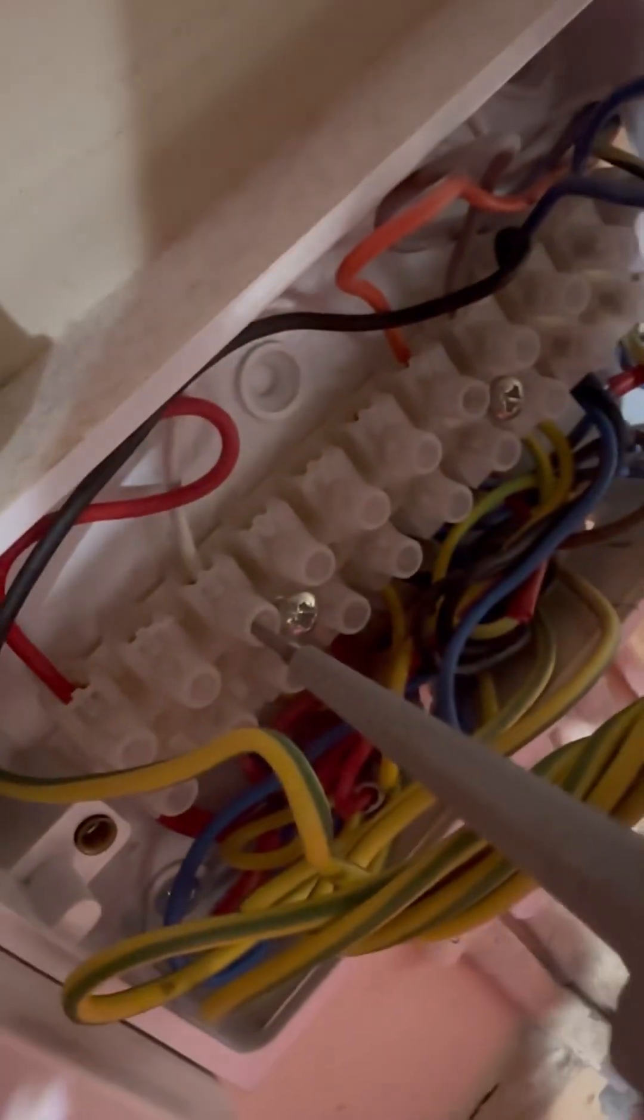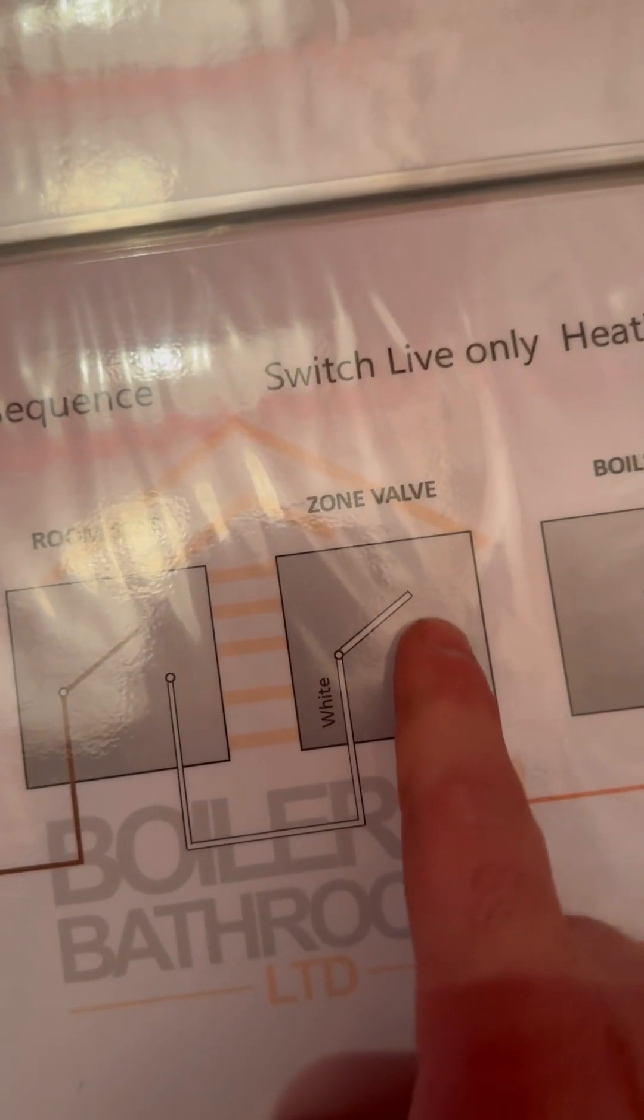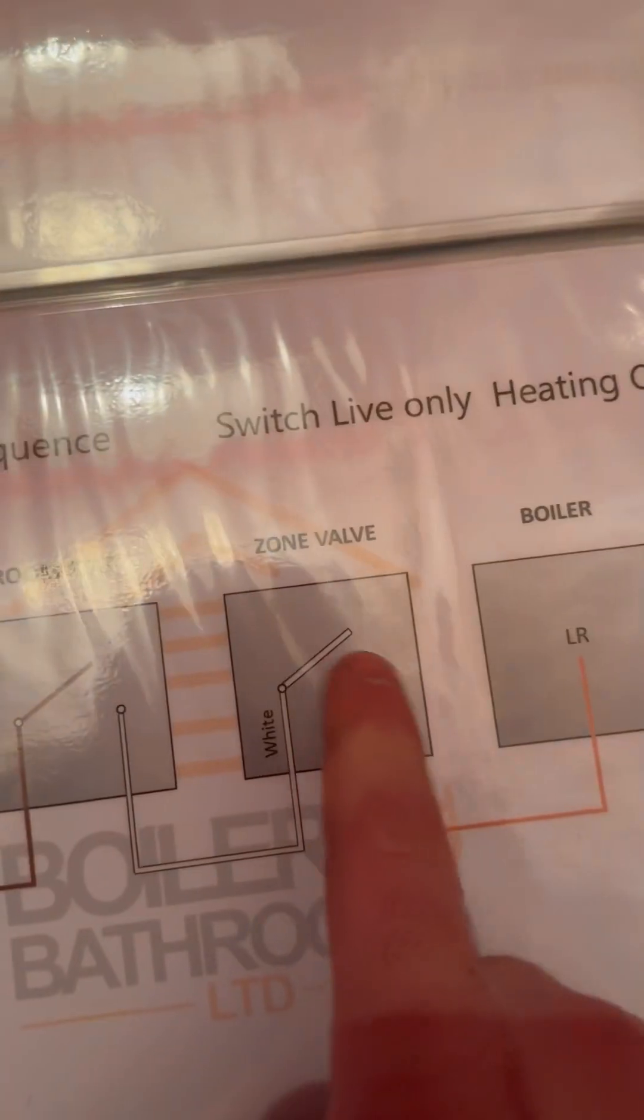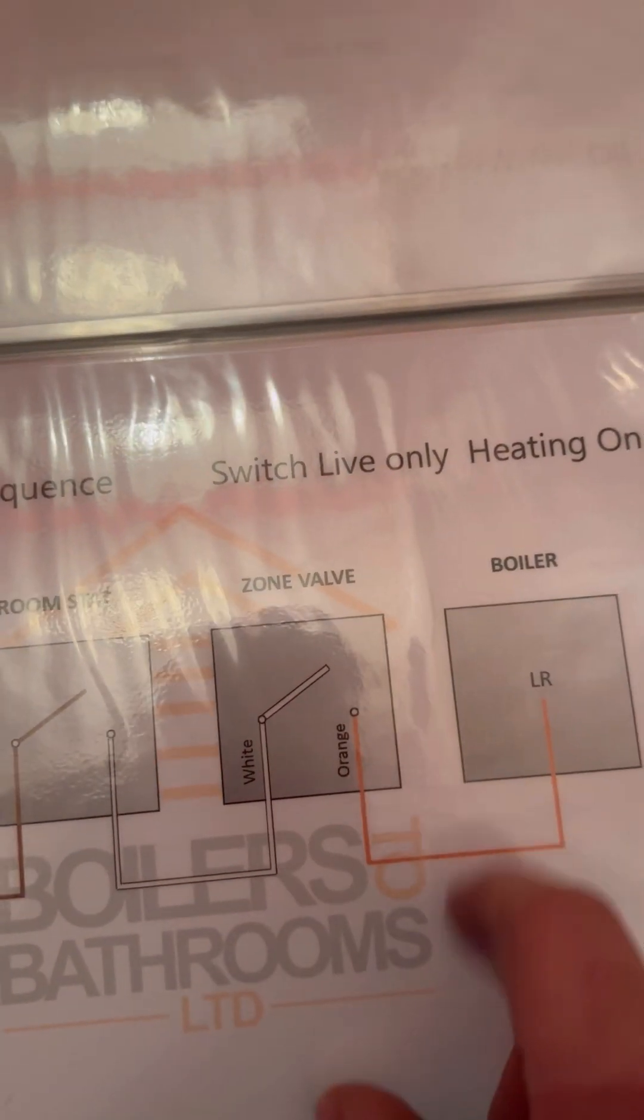So we're going to check on the white. We're getting 240 on the white cable, so we know that the room stat and the programmer is okay. Check for voltage on the orange. 20 volts isn't enough. So we know it's a zone valve at fault.